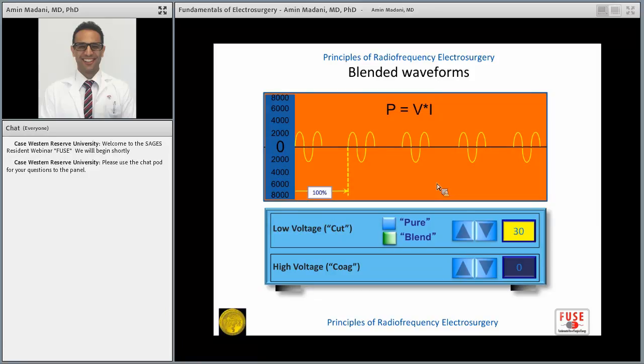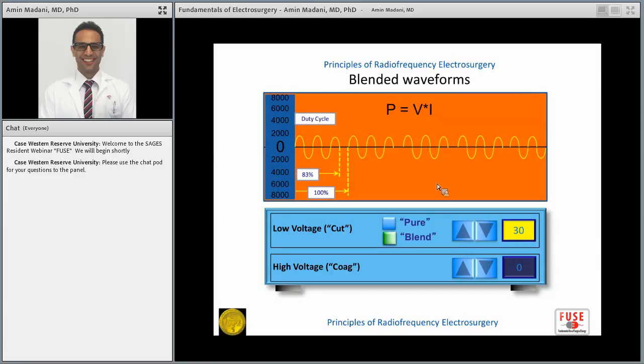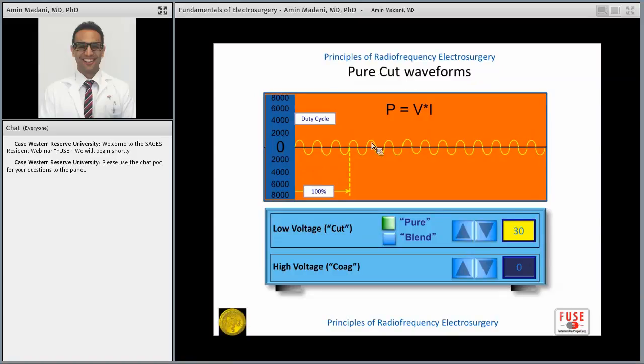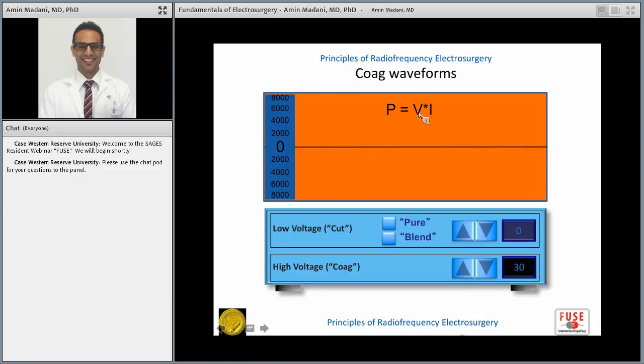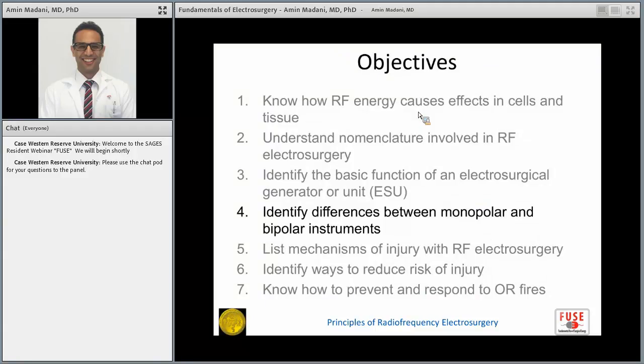So in this case, you have a 50% duty cycle. Or you can have different duty cycles, so 66% or 83%, and that depends on the manufacturer and the different blend settings. Okay, and if you go to cut, you eventually have the lowest voltage. And if you go to coag again, you have the highest voltage. Okay, I hope that clarifies some of the differences between cut and coag.